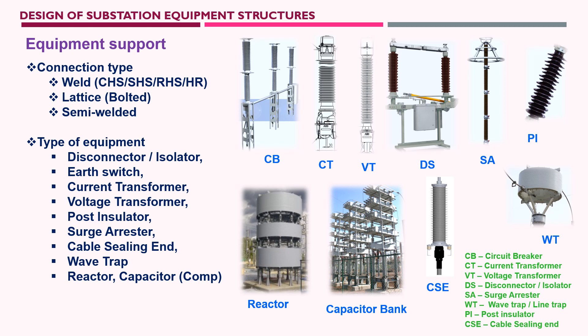A surge arrestor arrests lightning or any fault surge occurring in the substation area due to external environmental effects. PI (post insulator) is simply an insulated support. Reactor and capacitor banks are mostly used for compensation or power quality solutions. CSE (cable sealing end) is the terminal point between the overhead line and the ground cable trench. A wave trap arrests unwanted waves from telecommunications or communication networks that could disturb the substation system.